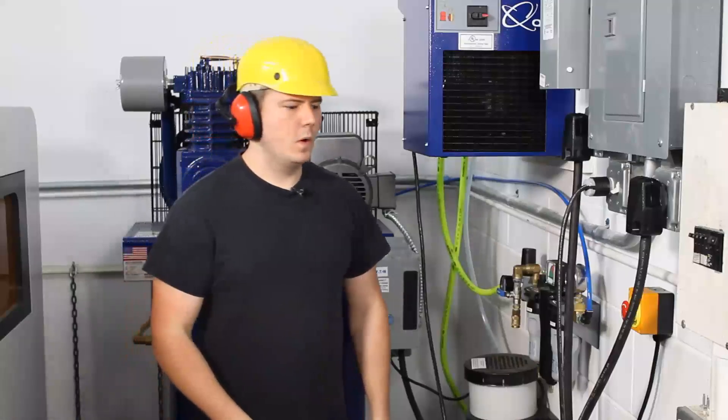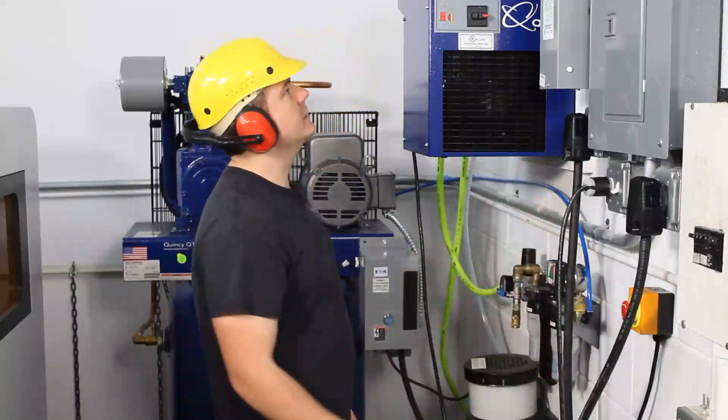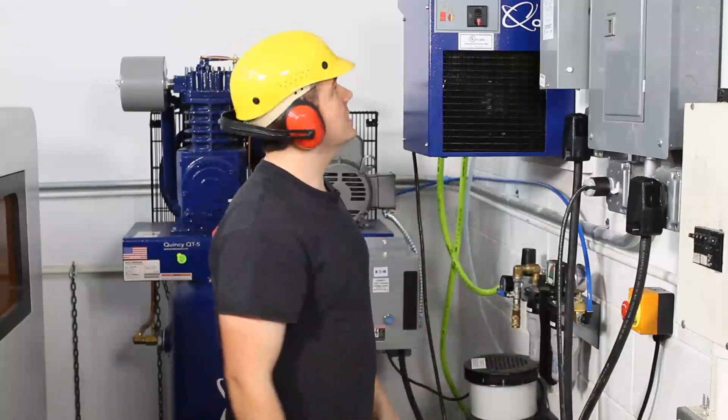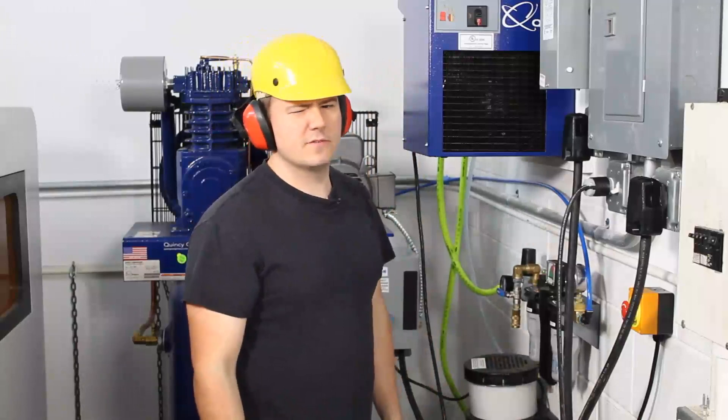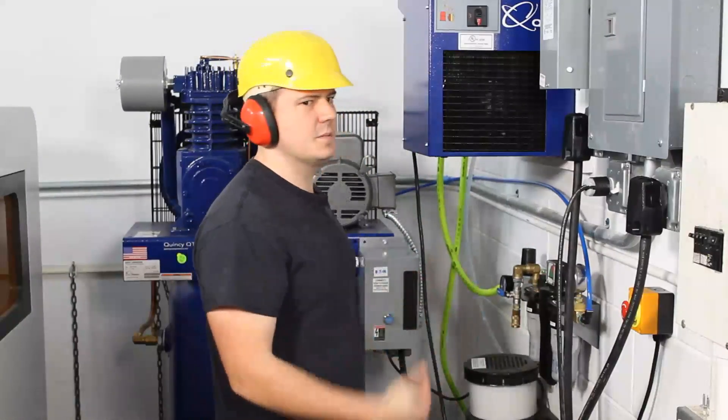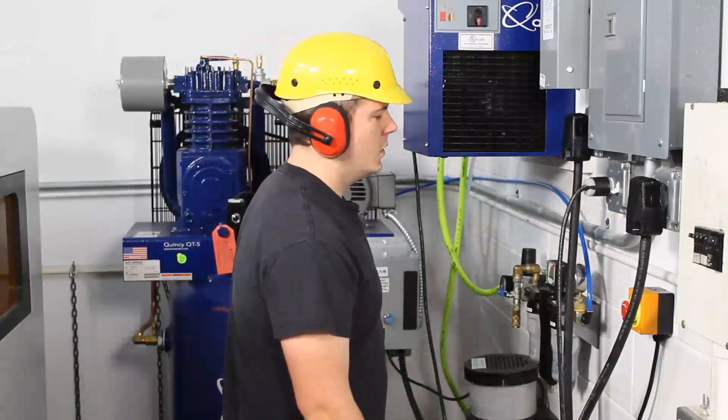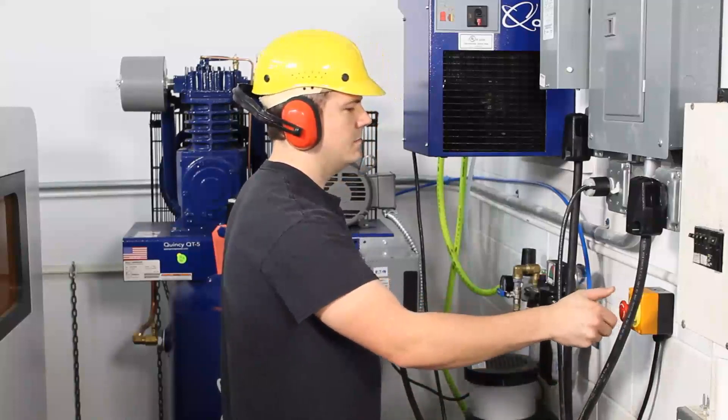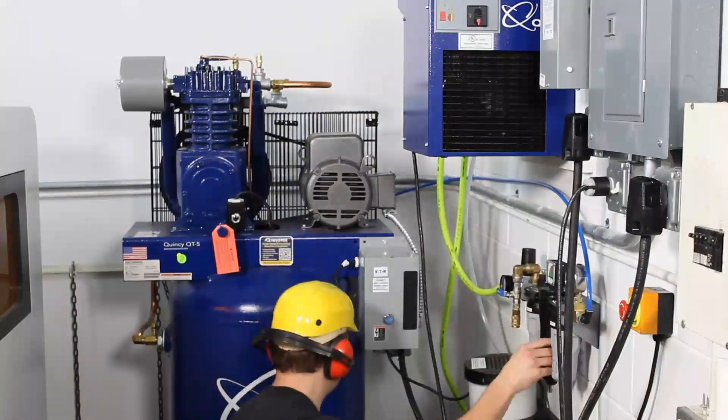So to start the compressor up, what we're going to do, we're going to have everything plugged in. We're going to turn our dryer on first. Give that just a little bit to cool down. It goes to 38 Fahrenheit. Of course, if you're in a different country, it'll probably be in Celsius. It's very near freezing, but just above it. Once that cools down a little bit, we'll go ahead and turn the compressor on. Okay, so it's still above its set pressure, so we're going to open up this valve here.